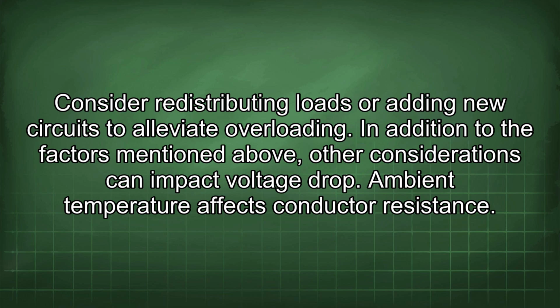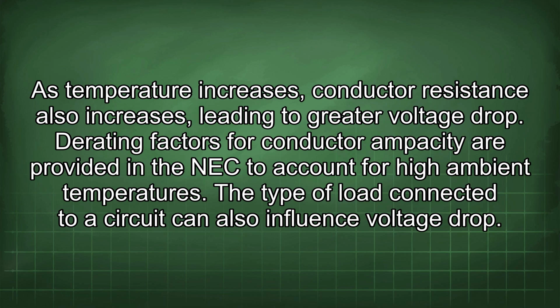In addition to the factors mentioned above, other considerations can impact voltage drop. Ambient temperature affects conductor resistance. As temperature increases, conductor resistance also increases, leading to greater voltage drop. Derating factors for conductor ampacity are provided in the NEC to account for high ambient temperatures.